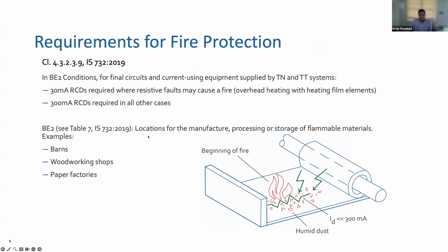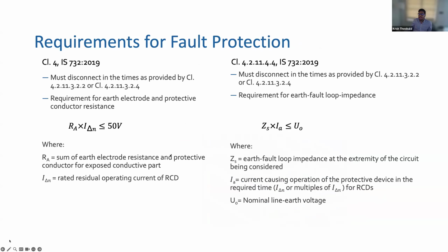What is a BE2 location? It is where you have manufacturing, processing, or storage of flammable material, like a barn, woodworking shop, or paper factory. Where do you need fault protection? Fault protection is required in two cases. In a TN system, if you are not able to meet the earth fault impedance requirements.